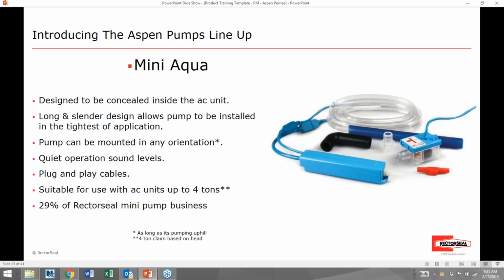Moving on to our number 2 pump, the Mini Aqua. The Mini Aqua has a fantastic slender design, which is designed to be concealed inside the unit. Because it's long and slender, it allows the pump to be installed in the types of applications where the line sets come out of one side of the mini split and cross all the way across the back before going out the penetration in the wall. Then you would have the opportunity to place the Mini Aqua in line with those line sets. It's the only pump of its size. There's nothing this small that has this much performance, and there's no other pump that can be installed in these super tight applications.